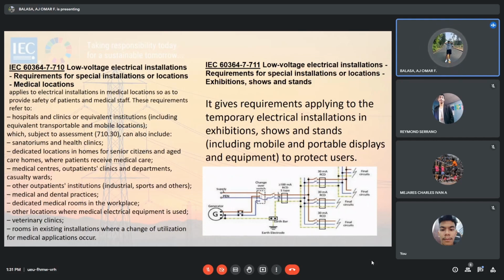In addition to the consideration of risk from electric shock, some kinds of electrical equipment like life support equipment and surgical equipment perform such vital function that loss of supply would pose an unacceptable risk to patients. Medical location where such equipment is used will require secure supplies. This has implication not only for the provision of safety power supplies, but can also render some conventional protective measures unsuitable. For example, when protecting circuits supplying critical medical equipment, restrictions are stipulated on the use of RCDs.